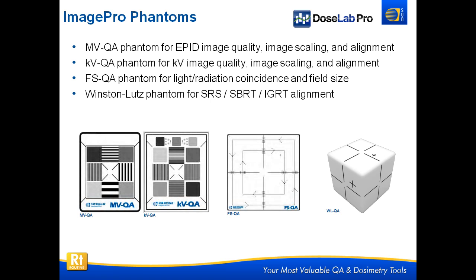DoseLab can also come with ImagePro Phantoms made by SunNuclear. These are not required, but they're extremely nice phantoms. We have the MVQA Phantom, which does all of your EPID image quality, image scaling, and alignment. A KVQA Phantom for KV image quality, scaling, and alignment — very similar, just one for MV and one for KV. The field size QA Phantom has hash marks printed on it so you can do your light field size measurements, and you can also do light radiation field coincidence because it has embedded BBs for both 10x10 and 15x15 fields.